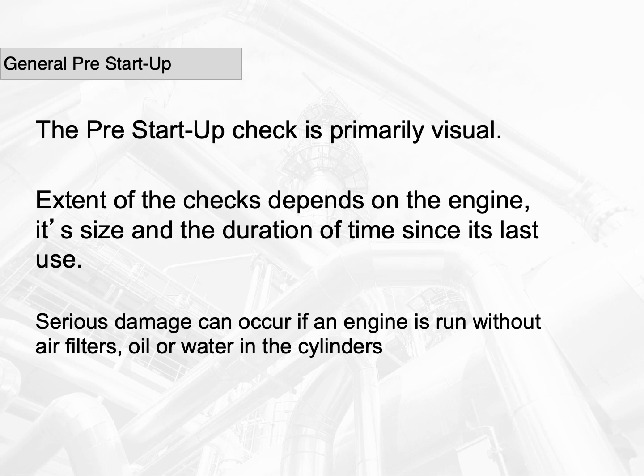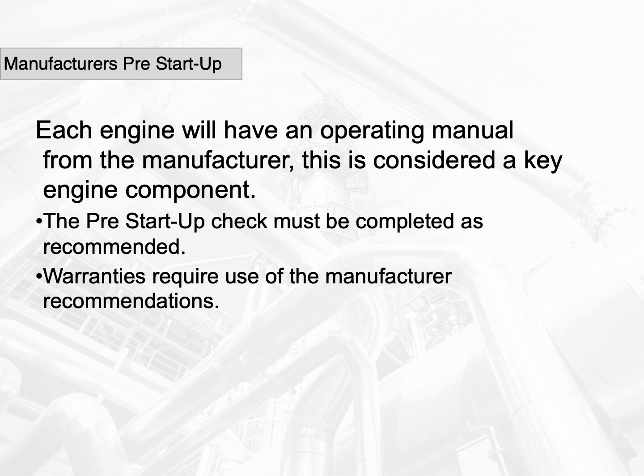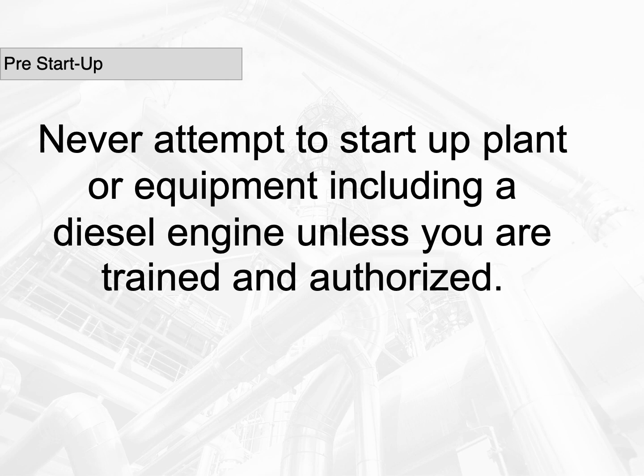Serious damage can occur if an engine is run without air filters, oil, or water in the cylinders. The importance of the visual inspection and understanding your equipment is vital for a successful startup. Each engine will have an operating manual from the manufacturer. This is considered a key engine component. The pre-startup check must be completed as recommended. Warranties require use of the manufacturer recommendations. Never attempt to start up a plant or equipment, including a diesel engine, unless you are trained and authorized.